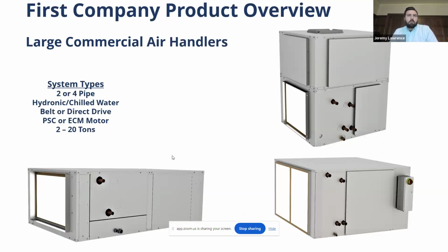These units are the most common that First Company deals with in the GTA. When we talk about fan coils, the most common names that come up are Unilux, Trane, ICI. There's a few others, and those are the ones that are typically being installed with the heating pipe risers right into condo buildings in the suites. And that business is pretty well set up direct from the manufacturer, past any sort of distributor, wholesaler, contractor, and typically these are sold directly to the developer.